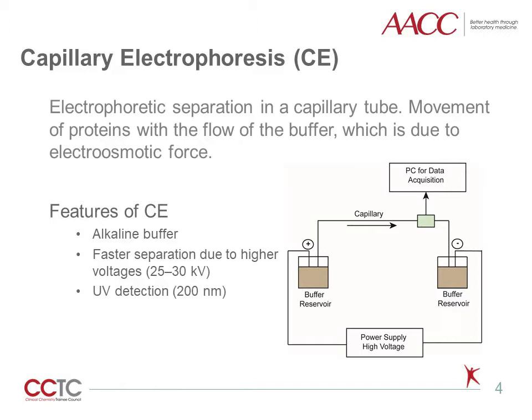Capillary electrophoresis is a separation technique where electrophoresis is performed in a capillary tube with the application of high voltage. CE consists of a high voltage power supply, a sample introduction system, a capillary tube, a detector, and an output device. Capillary tubes are usually composed of fused silica with an internal diameter of only 20 to 100 micrometers. The fused silica contains silanol groups that become ionized in an alkaline buffer, creating an electric double layer producing a flow of buffer towards the cathode. This electroosmotic flow causes most proteins to travel in the same direction regardless of their charge. Proteins move from anode to cathode and are detected usually with 200 nanometer wavelength UV light, but also through electrochemical, fluorescence, conductance, or mass spectrometry methods. CE is popular in clinical laboratories because of fast throughput and utilization of small sample volume.